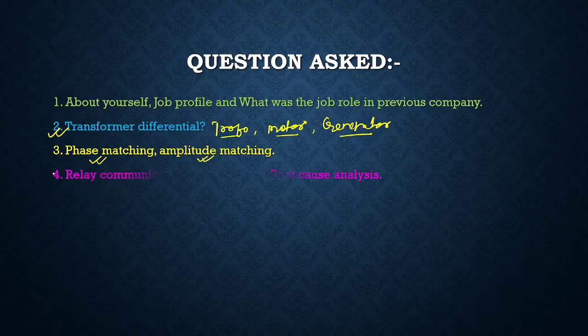The next questions I encountered were on relay communication, fault analysis and root cause analysis. Do you have any idea about root cause analysis? How do you analyze a fault if any fault has happened in the switchgear and power system? How do you act? Generally, whenever any fault occurs, we go and check the fault records and event records, so it is very necessary to communicate with those relays using software. You can also check the faults manually, but checking by communicating with the relay is better. You will have all the magnitude curves and details so that you can find the exact root cause. Since tripping occurs in cascade, you can see which feeder tripped, and then which feeder tripped further. So you will have a basic analysis of all the tripping records.